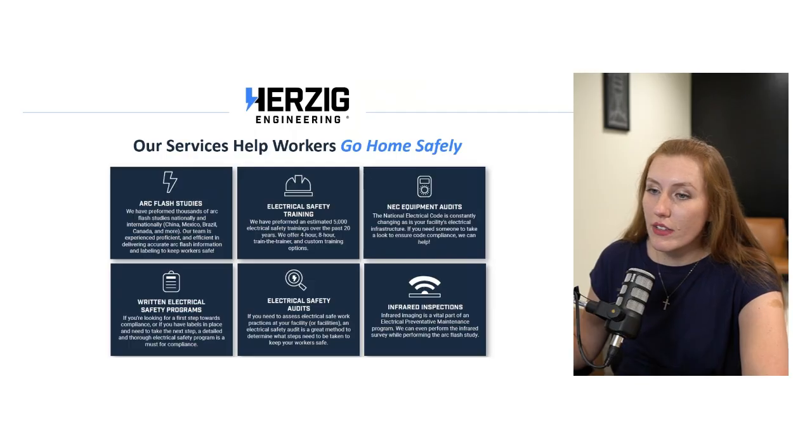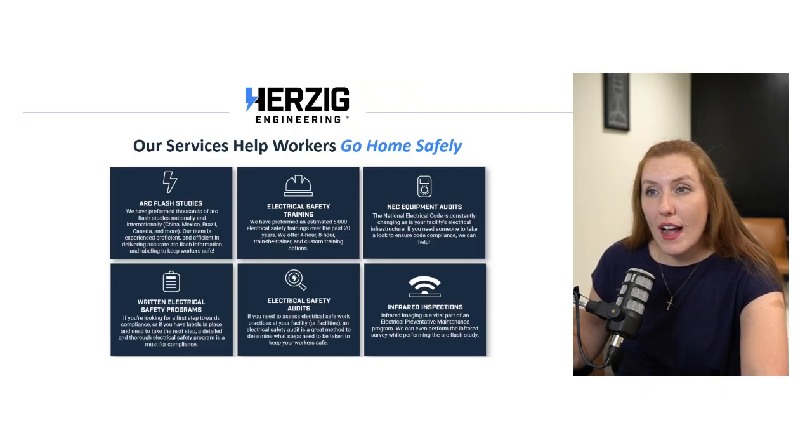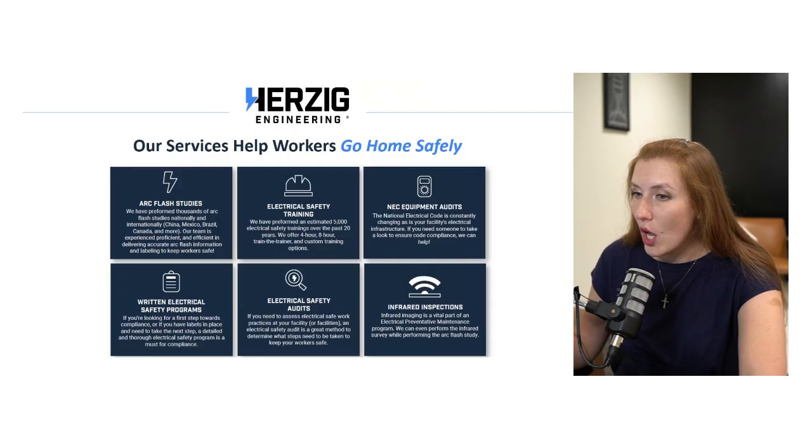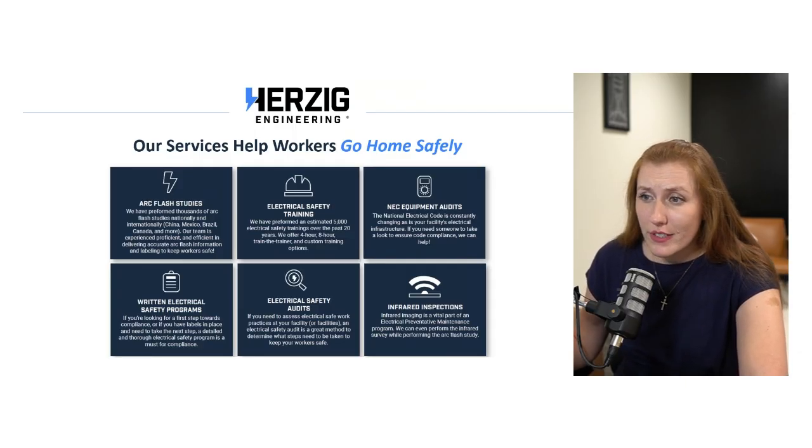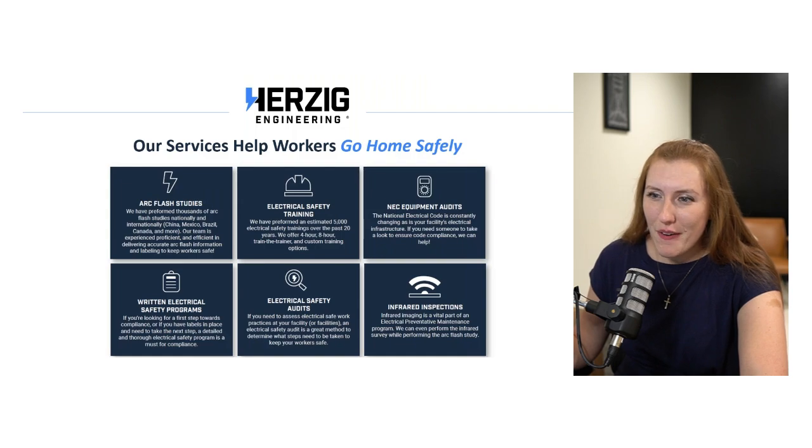If there are 11,000 volt switchgears and all panel doors are closed, will they affect persons near it? Possibly. It depends on how they're interacting with it. Are they turning it off and on? Are they replacing any components? Have there been any issues with it previously? What is the condition of that equipment? How long ago was it last serviced or maintained, if at all?